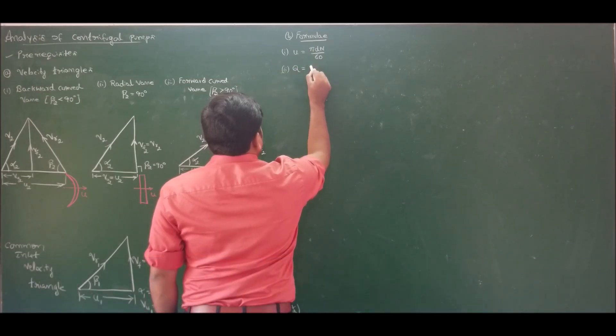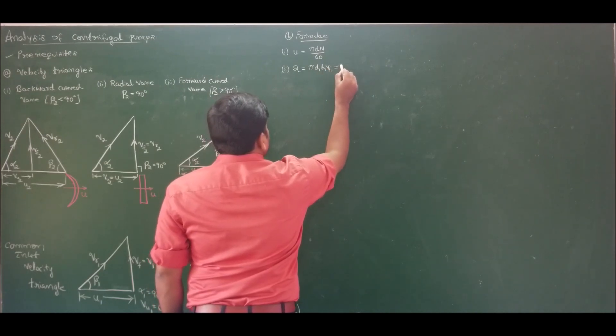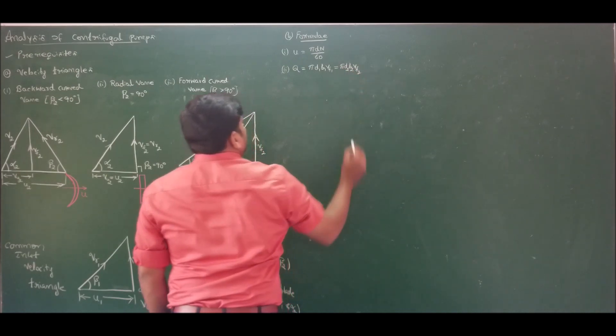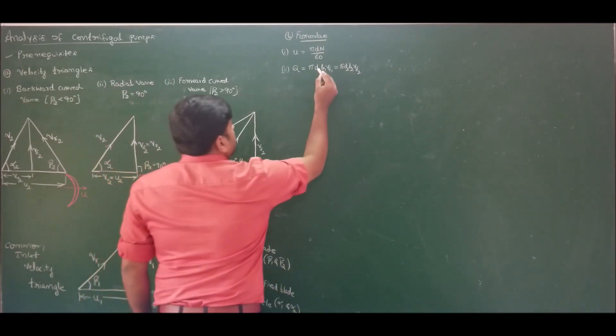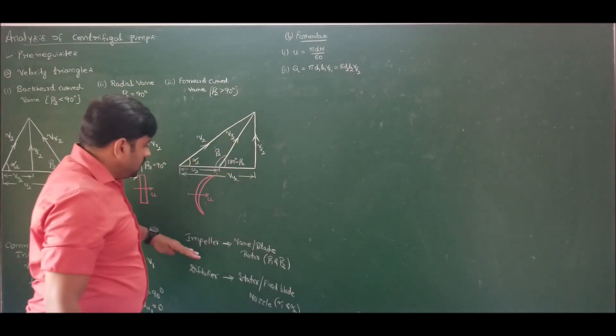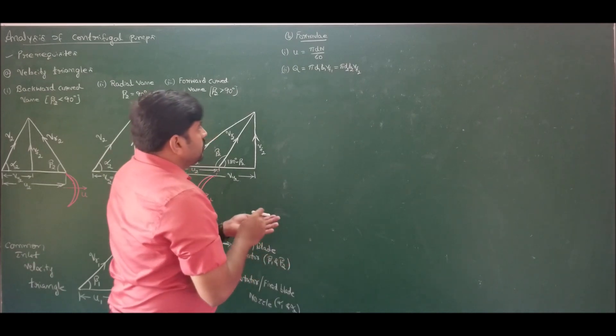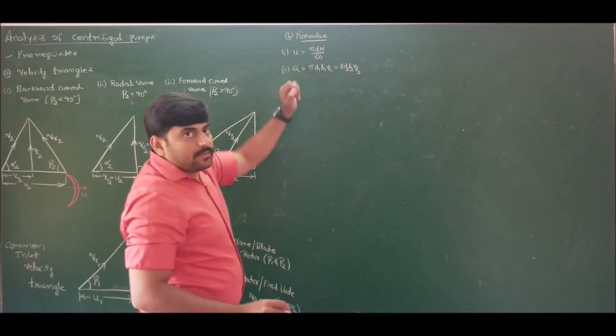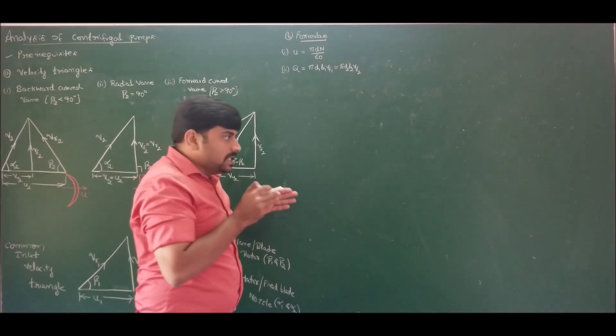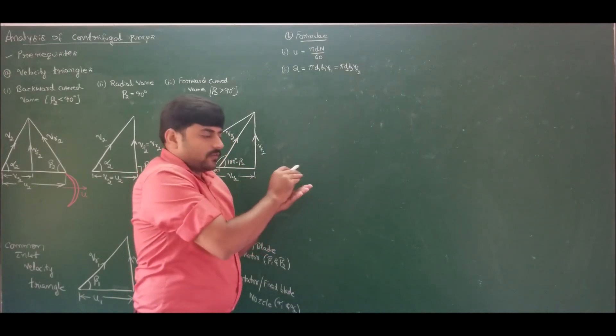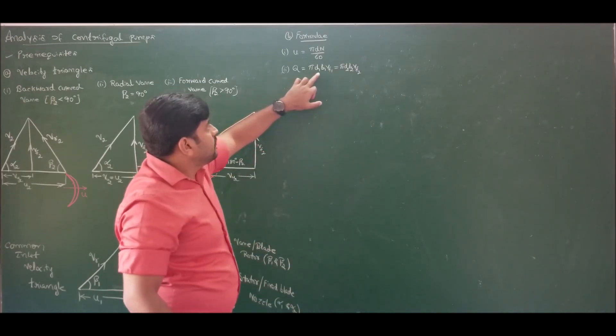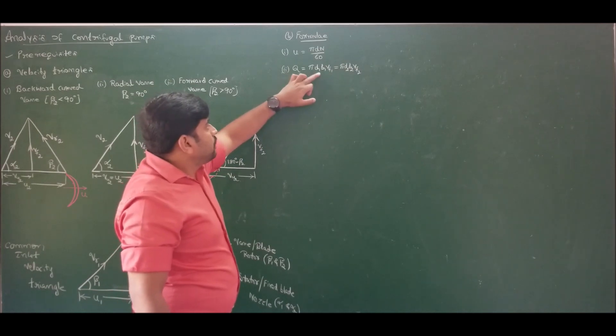Next, the formula for discharge Q equals π·D1·B1·Vf1, which also equals π·D2·B2·Vf2, where D1 and D2 are the impeller diameters at inlet and exit, and B1 and B2 are the width of the blade. We use circumferential area because water moves on the surface of the blade, not inside it. Therefore we use surface area, which is circumference times thickness, giving π·D·B. Also, if you know the pipe diameter, discharge equals π·ds²/4 times flow velocity at inlet, where ds is the suction pipe diameter — here we use cross-sectional area since water flows inside the pipe.